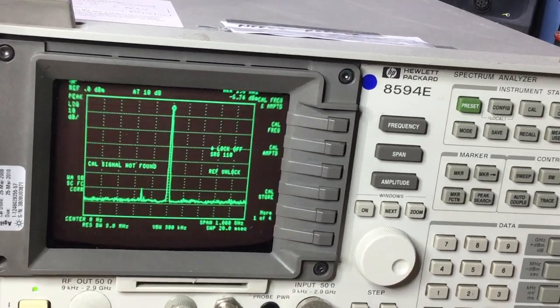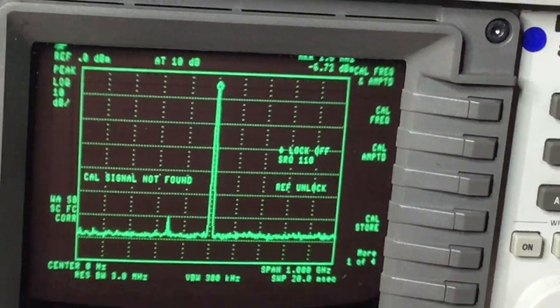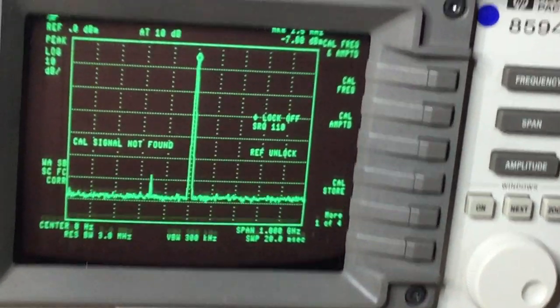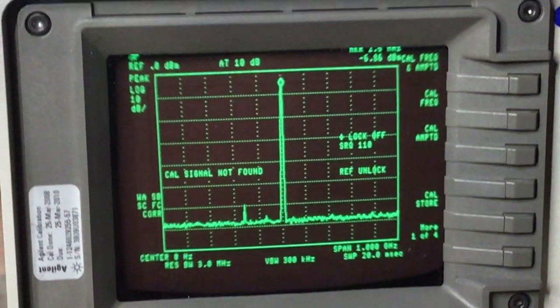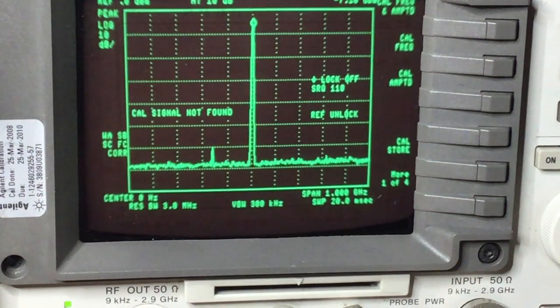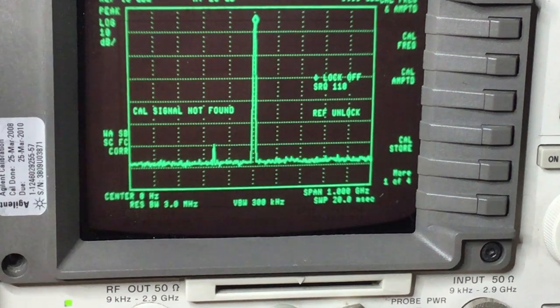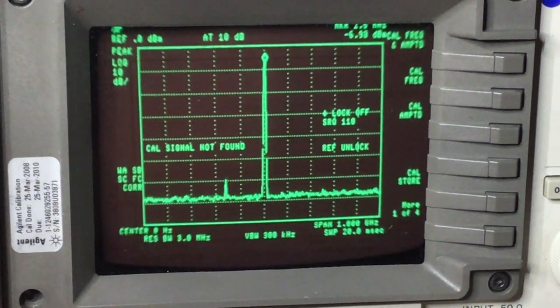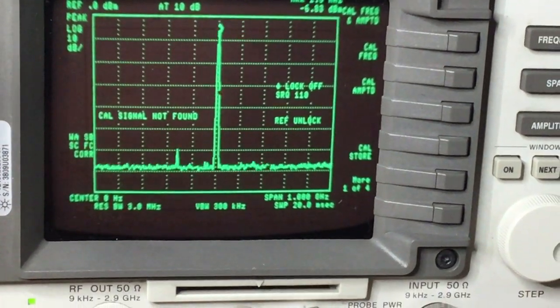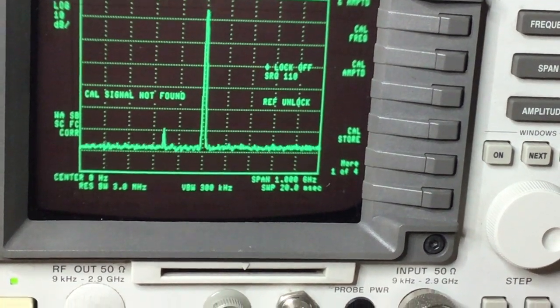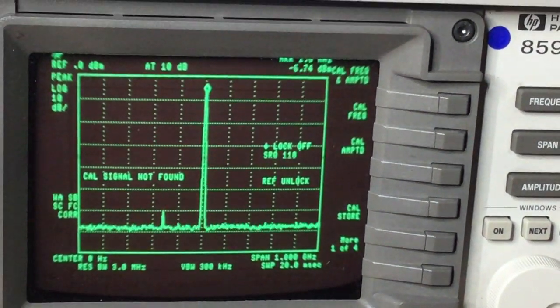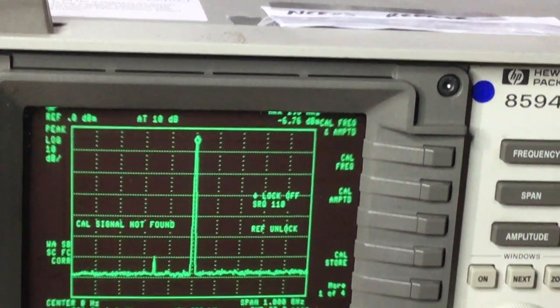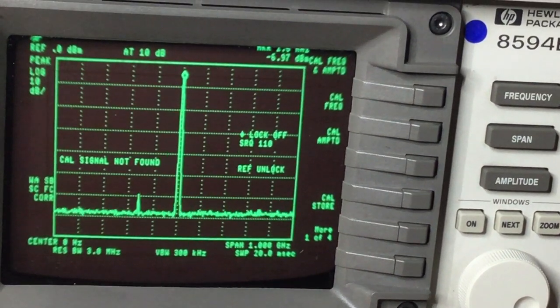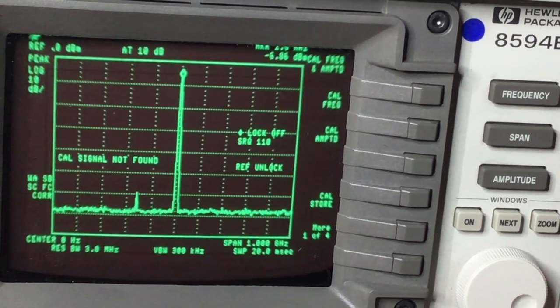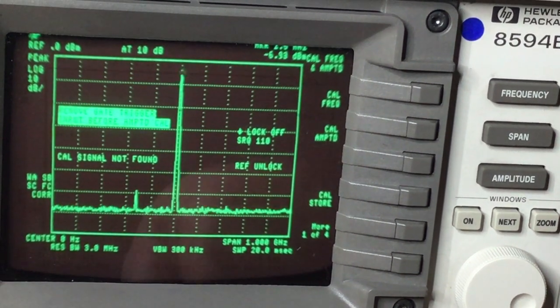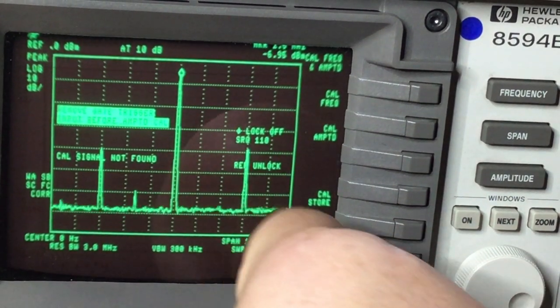Very strange already. The screen's a bit blurred. I'll have to figure out how to change the focus on the monitor because it's a bit blurred out. Cal signal not found. Center frequency 0 Hz. So it's obviously not found the 300 megahertz calibration signal then, which is strange. Very strange. Okay, right, I'll go back to cal again. Reconnect that BNC and then we'll see.